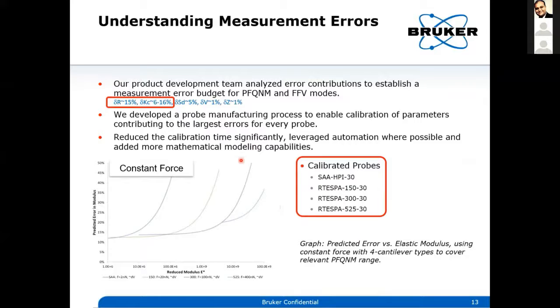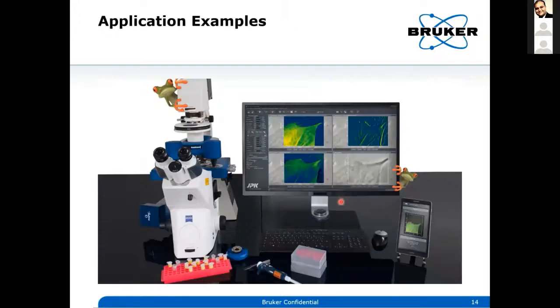So here is an example. If you choose the wrong probe, you get the radius and the spring constant wrong. If you get the correct numbers, then it's good. If you get them wrong, the errors can be significant. So if I'm measuring this modulus, this is the predicted error. If you choose the wrong probe, your error can be as high as 50%, right? So it's very important we choose this correctly, based on our estimation of where the modulus is going to fall.